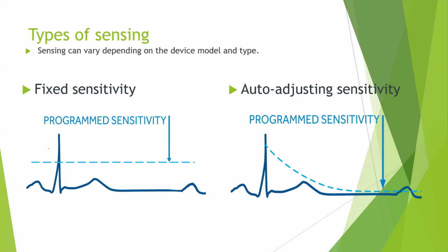So there are two types of sensitivity detection by the device. There is what we call fixed sensitivity. Here you program, for example, a fixed number, and the device will try to detect, for example, the R wave or the P wave based on that number. And most pacemakers, or almost all pacemakers, will use a fixed programmed sensitivity number.